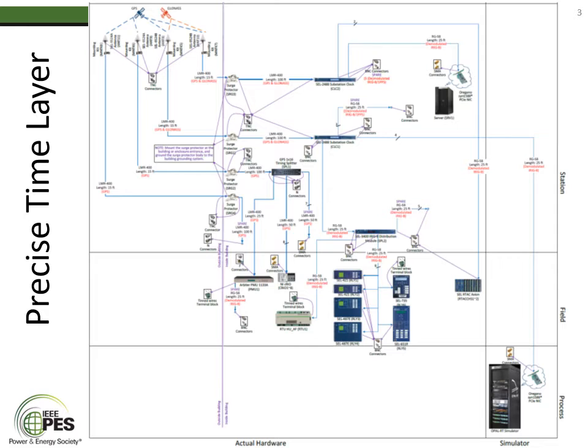First, it is important to use appropriate type of coax cable, ideally LMR400 for transmission of GNSS signals. Other types of coax cables, such as RG58, are not suitable because their attenuation is severe at the frequency of the GNSS signals. Of course, RG58 is still good enough for transmitting signals with lower frequencies, such as IRIG-B.